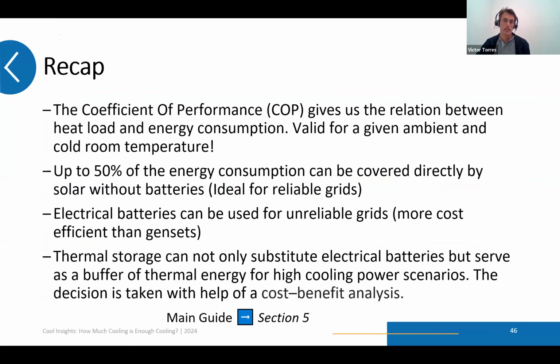So the recap of the considerations for the design is to make sure the coefficient of performance is well analyzed. You need to get this from the manufacturer. The COP gives us the relationship between heat demand and energy consumption, and it is only valid for a given ambient temperature and cold room temperature. If the ambient temperature changes because you're designing for another location, or you have another cold room temperature because you have another product inside, then the COP will also change.